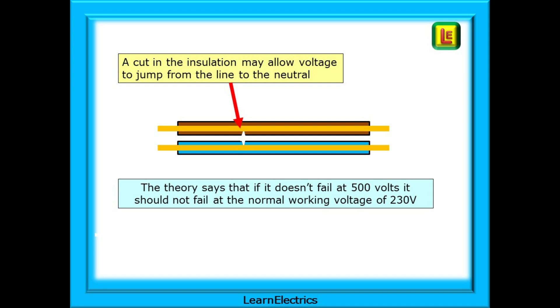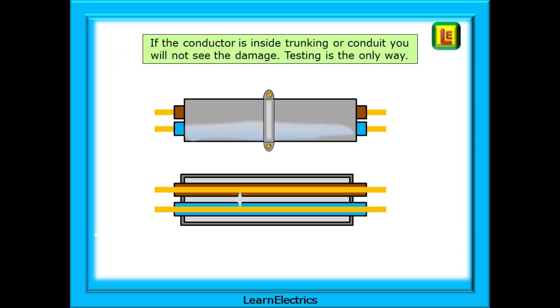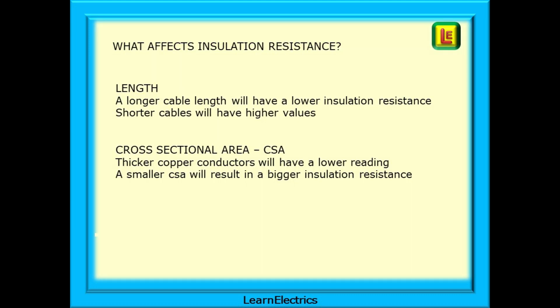Why are we testing? A cut in the plastic insulation may allow the voltage to jump from the line to the neutral, a danger to the customer and causing the protective devices to trip. The theory says that if the insulation does not fail at 500 volts it should not fail at the normal working voltage of 230 volts. How can we tell if the cable is damaged without testing if the cables are in conduit, trunking, or plastered into walls? We must test if we want to be certain that all is okay. The two main factors that can alter the results are the length of the conductor and the cross-sectional area or size of the conductor. A longer cable length will have a lower insulation resistance, and thicker copper conductors will also have a lower reading, while a smaller CSA will result in a bigger insulation resistance value.